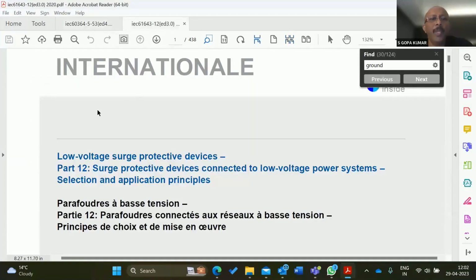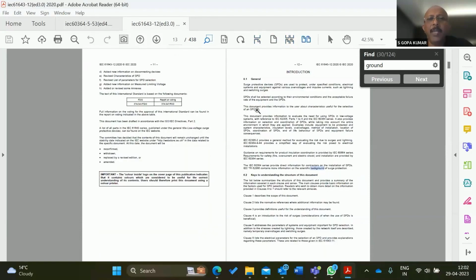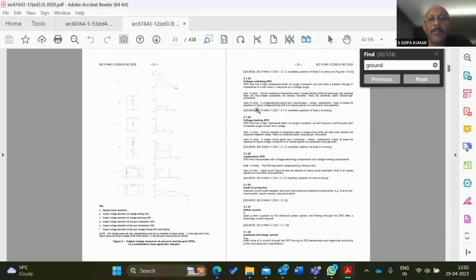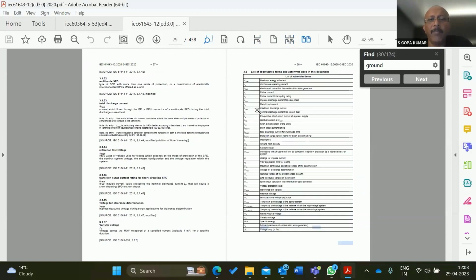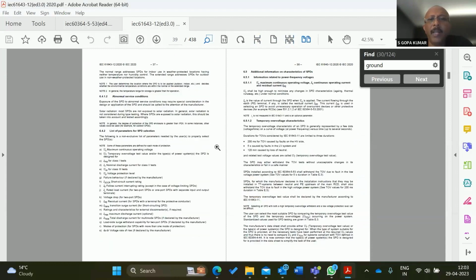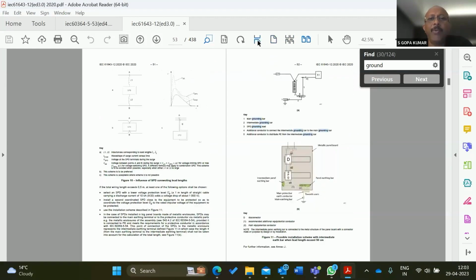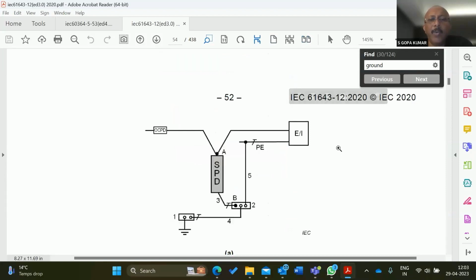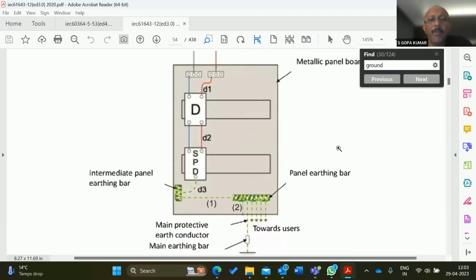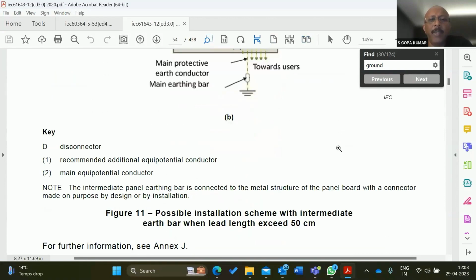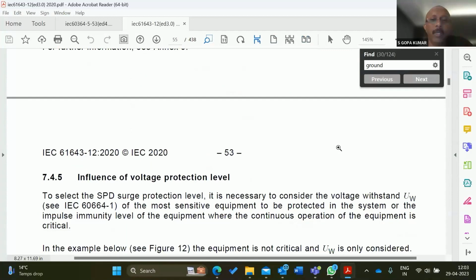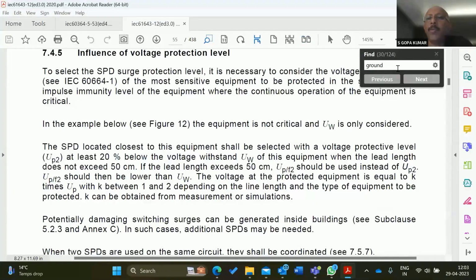One moment, I am just showing you the standard on surge protection selection and erection, which is a new standard. It is one of the biggest standards published in recent days. It has about 215 pages. A lot of new information is shown here. For example, if you want to use an SPD with, let's say, a V-type connection, how to make the V-type connection, if you use it in a panel board, how to make it and how you can reduce the length of the wire, and all such information is included in the standard.